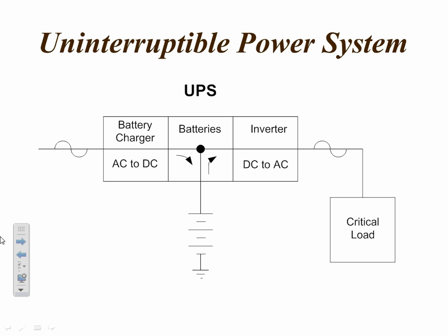So if you think about it, if we were to lose power out here, this power would still be there because the inverter is still connected to the batteries, and up until a second ago, the batteries were still being charged by the charger. So now we're dependent, however, on the life of the batteries to keep producing this waveform through the inverter to the critical load. The power comes back, this waveform is restored, and again we'll immediately start to recharge the batteries again.